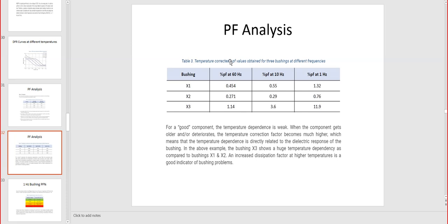So temperature corrected power factor, after the correction at 20 degrees: at 60 hertz, phase A is 0.454, at 10 hertz 0.55, and at 1 hertz 1.32. So it's not a complete graph, but there are 3 measurements taken at 1 hertz, 10 hertz, and 60 hertz. These are the values on the high voltage side bushing.